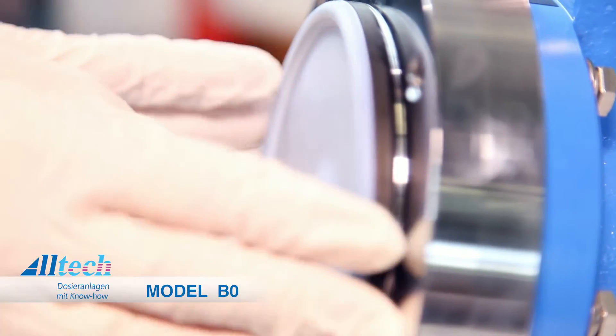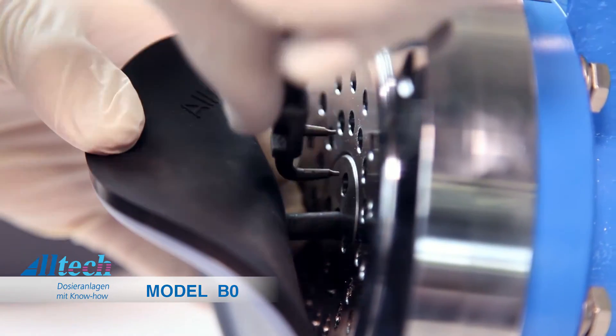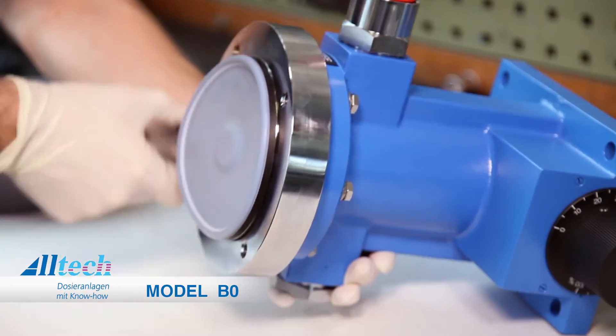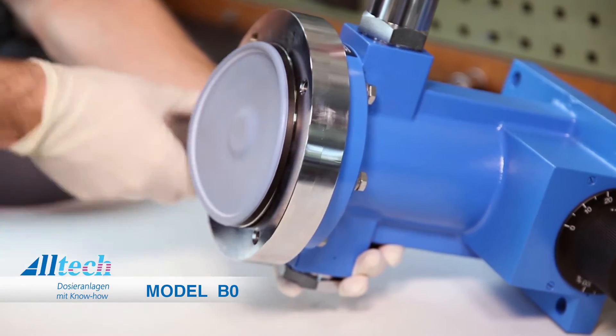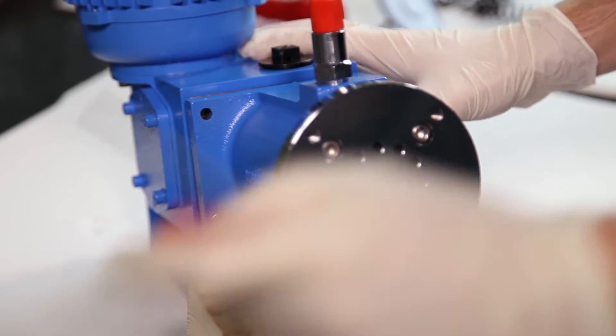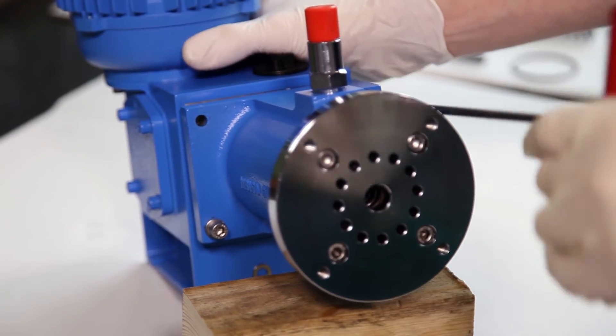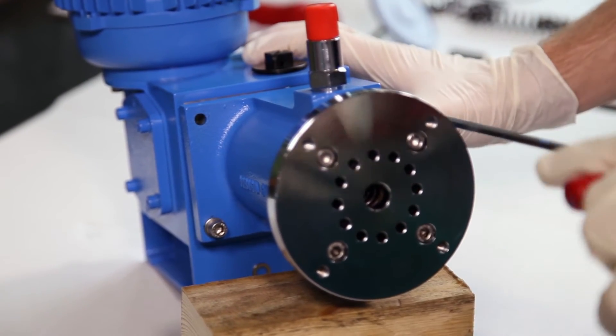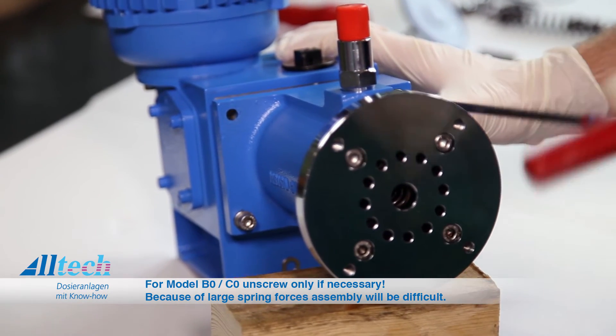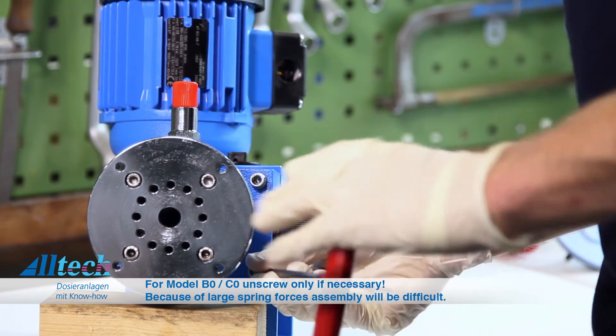For the bigger pumps, B0 and C0, the diaphragm support has to be unscrewed from the fixing plate to exchange the diaphragm. For pumps of that size, the regular replacement of the piston spring isn't necessary. To exchange the O-ring between piston flange and drive gear as well as the O-rings of the spindle, the piston flange is unscrewed. Pumps with a B0 or C0 drive gear should only be disassembled if necessary, as reassembling is difficult due to the strong elastic force of the piston spring.